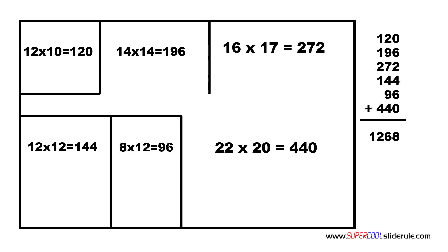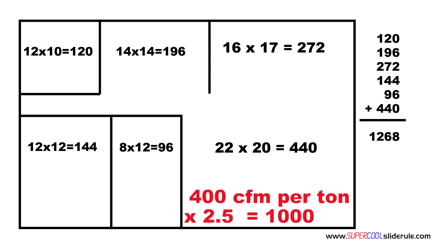We are going to assume that a proper heat load calculation has been performed and a 2.5 ton unit is required. The CFM output is 400 CFMs per ton. So multiply 400 by 2.5, our tonnage of the unit, and our answer is 1000. So the system output is 1000 CFM.